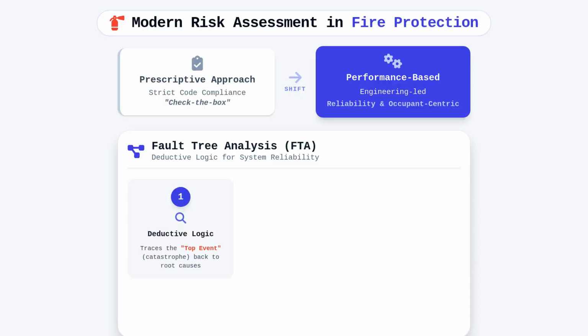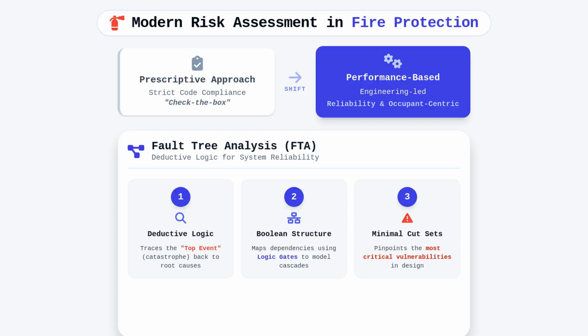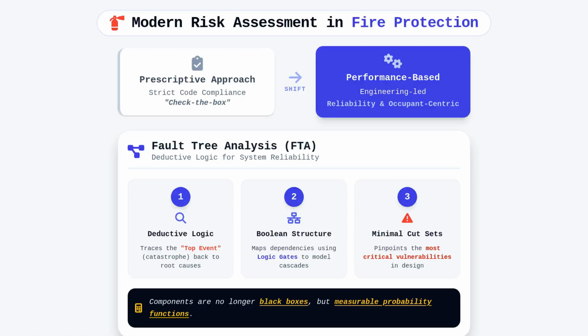It allows us to visualize how various independent component failures can cascade into a catastrophic top event, such as a full-scale fire spread. By breaking down the system into a Boolean structure, we identify the minimal cut sets that represent the most significant vulnerabilities in our architectural or mechanical designs. This approach forces us to treat every suppression component not as a black box, but as a probability function with a measurable rate of failure.